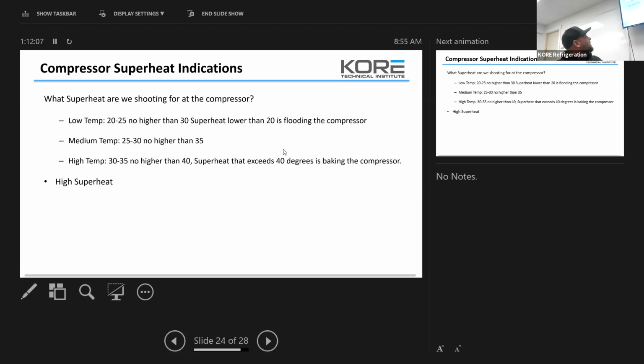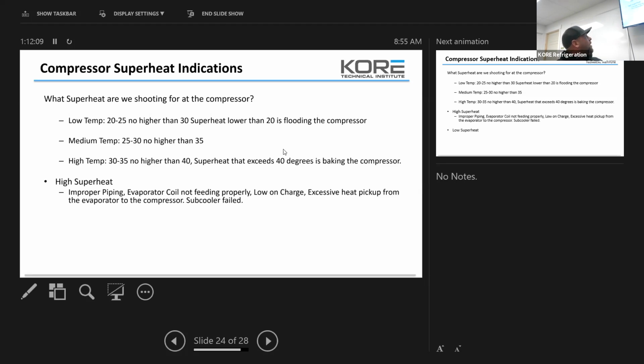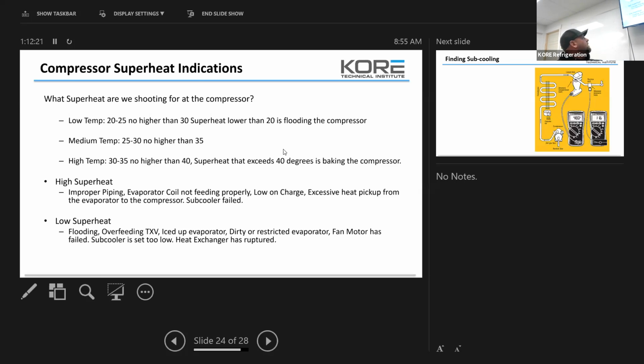Yeah, you bet. So high superheat: improper piping, evaporator coil not feeding properly, low on charge, excessive heat pickup from the evaporator to the compressor, subcooler failed. Okay. Low superheat: flooding, overfeeding TXV, iced up evaporator, dirty or restricted evaporator, fan motor has failed, subcooler is set too low, heat exchanger has ruptured. Okay. We've seen all of these conditions.